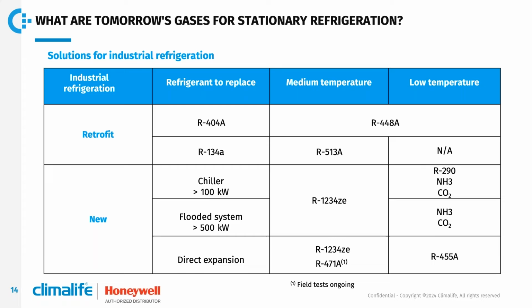Let's not forget that we also have reclaimed refrigerants for maintaining existing installations in service, which is a solution to avoid consuming quota. In new installations, we will see that for medium temp, in chillers, in flooded installations, or in DX systems, it is extremely simple. We have HFO 1234ZE, which is a refrigerant that all technologies agree on. It is also classified in group 2 of the PED, the same category as 134A. And in the low temperature, we have propane, ammonia, CO2, and R455A direct expansion systems.